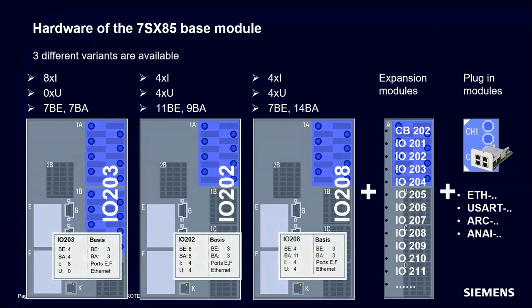These base devices can be used universally. All available functions can be configured with each of the basic variants. Missing analog inputs, such as current and voltage transformers, can be added in further expansion modules. So each base module can be used for transformer differential protection, and each base module can also be used for line protection. That means you can standardize on only one base module for all your protection applications. And this universal device can take over all functions of up to 12 individual type-related devices.